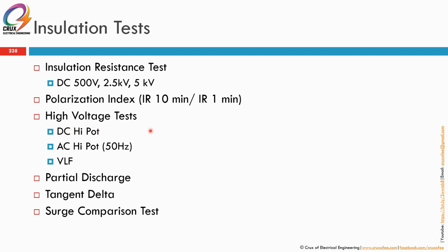Third is the high voltage test. You can have a DC high pot, AC high pot at 50 Hz, or VLF. For long cables you normally do a VLF or a DC high pot test. Next is partial discharge and tangent delta. These are tests considered optional, but normally we would do them during commissioning as a baseline for us to refer to in the future.